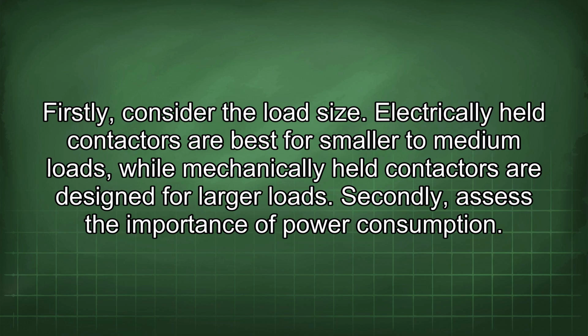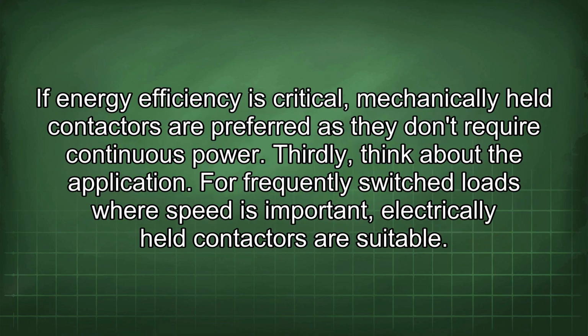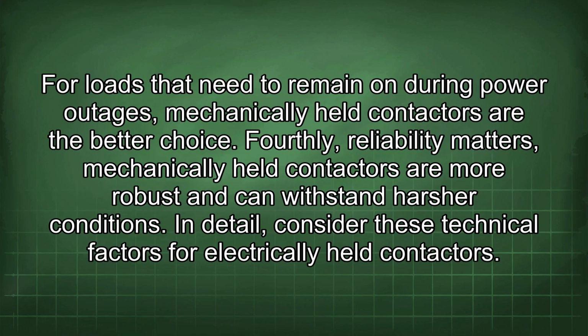Secondly, assess the importance of power consumption. If energy efficiency is critical, mechanically held contactors are preferred as they don't require continuous power. Thirdly, think about the application. For frequently switched loads where speed is important, electrically held contactors are suitable. For loads that need to remain on during power outages, mechanically held contactors are the better choice. Fourthly, reliability matters. Mechanically held contactors are more robust and can withstand harsher conditions.